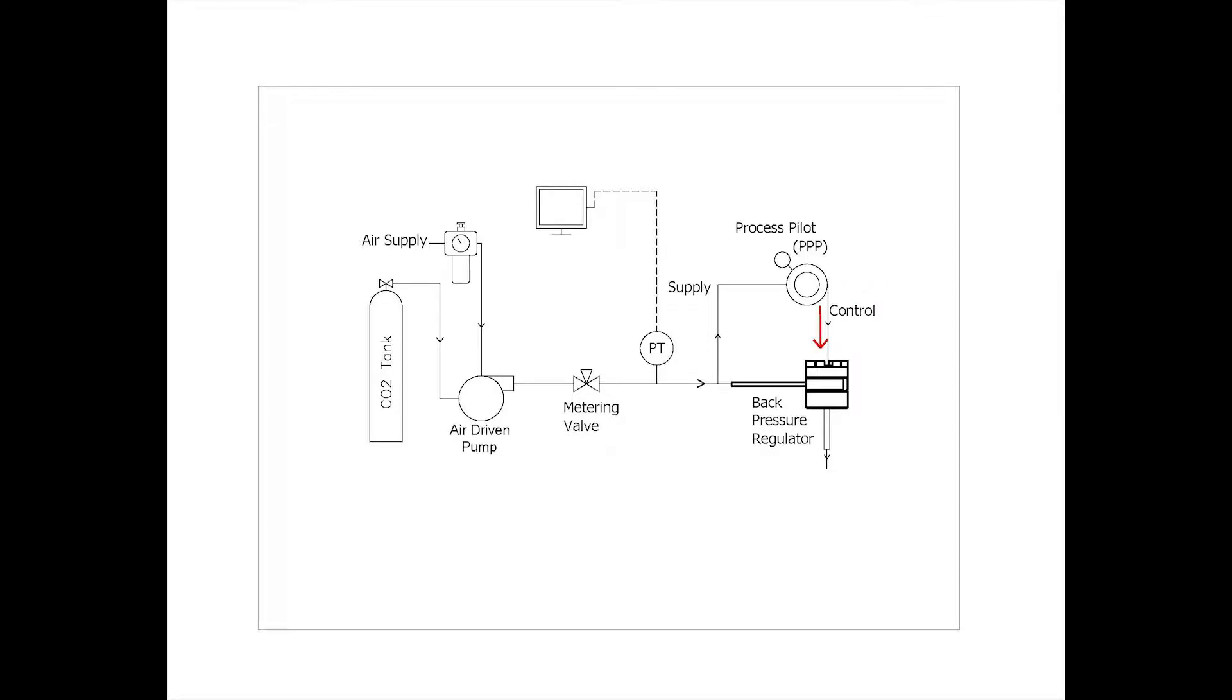As flow begins, both lines are pressurized together up to the setpoint of the pilot regulator. When system pressure slightly exceeds this setpoint on the dome of the Equilibar, flow is finally released through the BPR. We are measuring the BPR's inlet pressure in LabVIEW. Now let's go see the system in action.